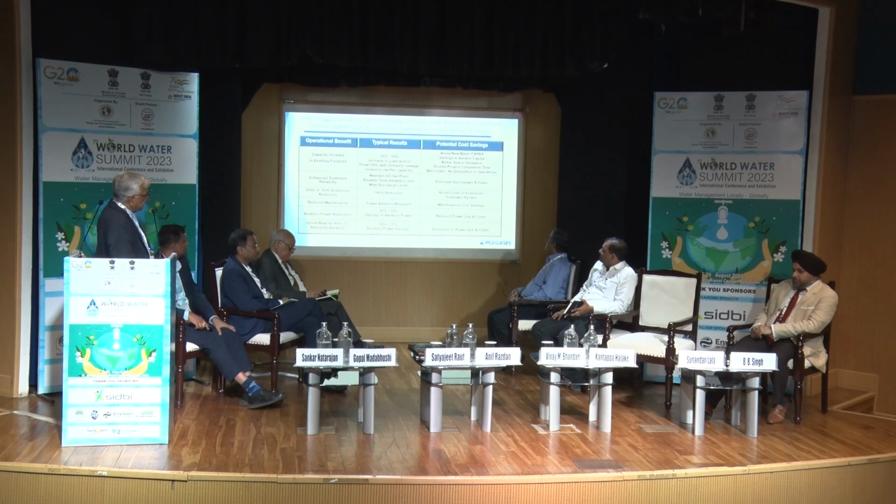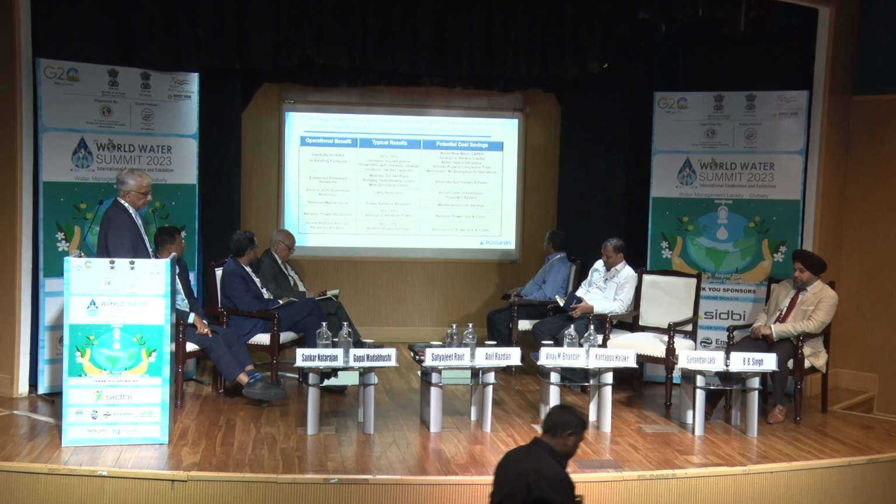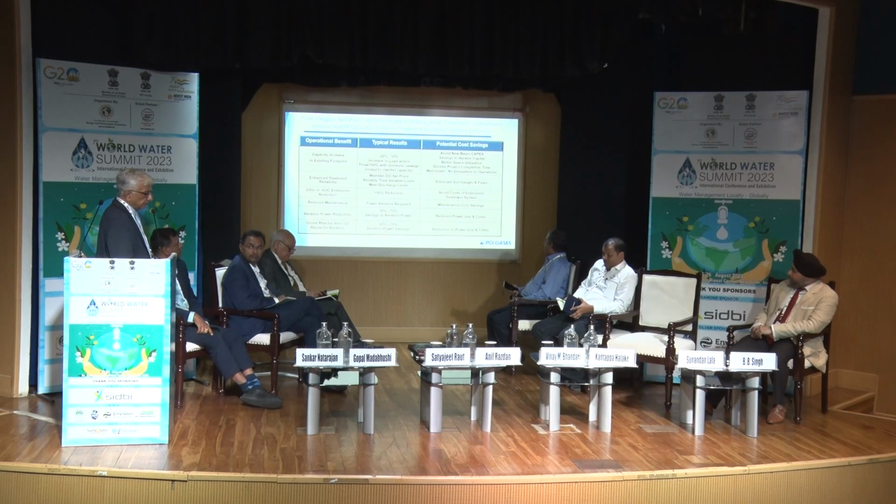And some of the advantages I've been trying to say is the capacity augmentation. If you have a sewage plant of 10 MLD, with clarifier permitting, we can go up to 20 MLD without any capital investment, using just the oxygen generator and some piping, which I will describe.